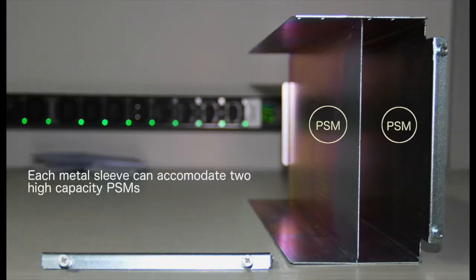The high-capacity DC and AC PSMs are smaller in size compared to the existing Delta and WYEDC PSMs. Therefore, you must install a metal sleeve in the PDU before installing the high-capacity PSM. Each metal sleeve can accommodate two PSMs.